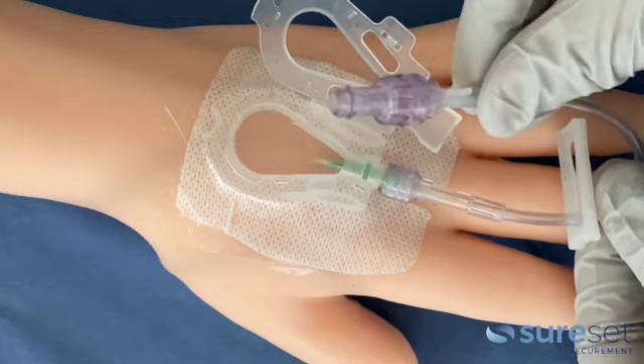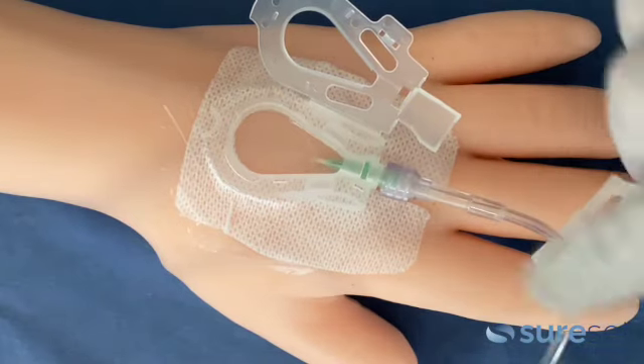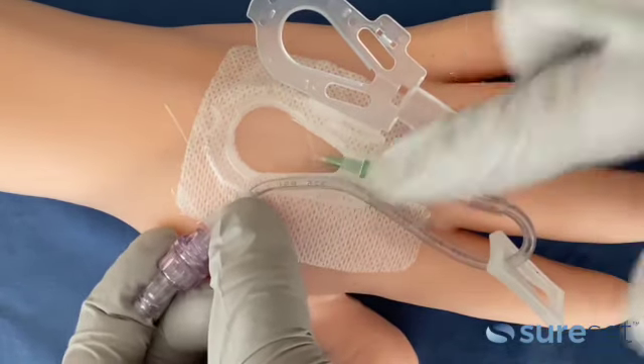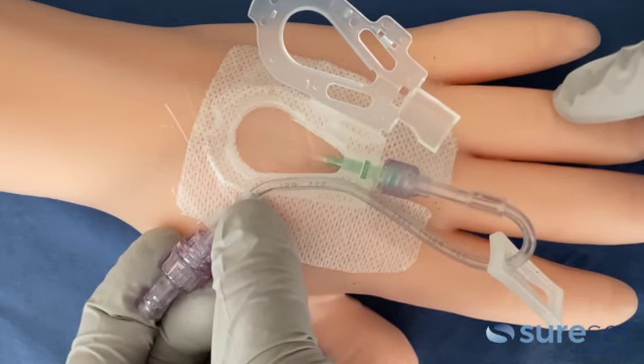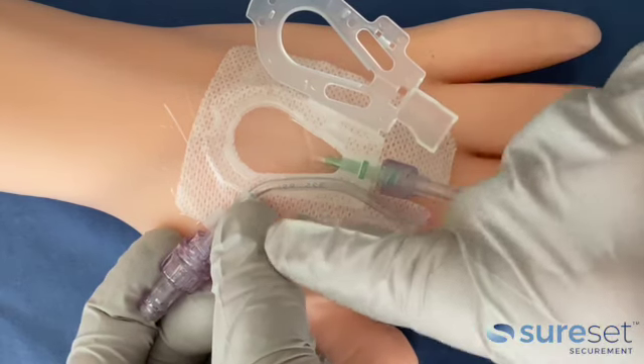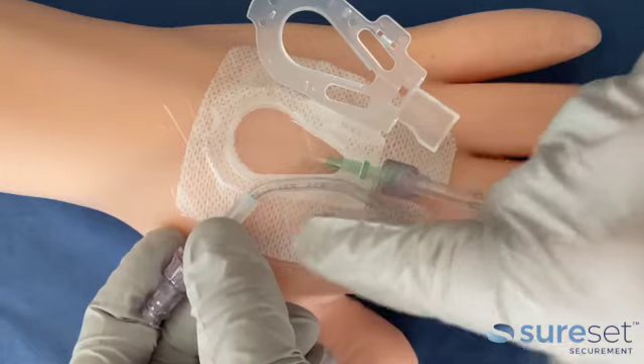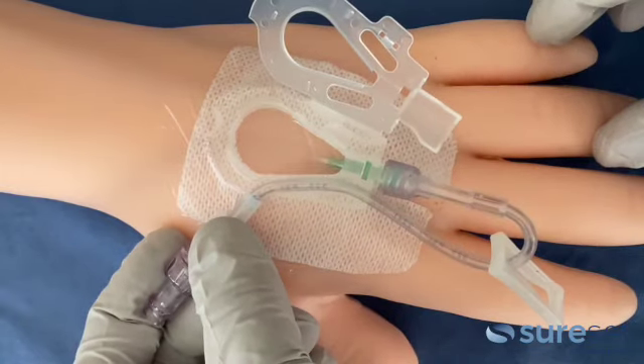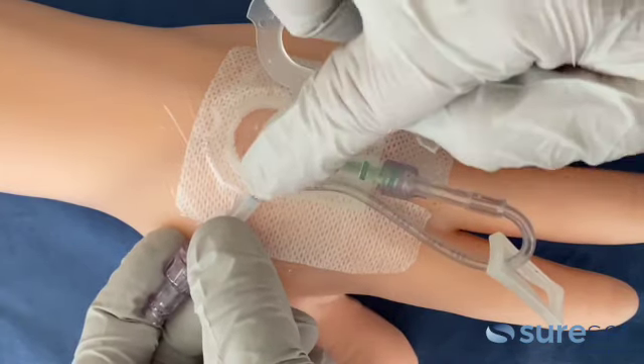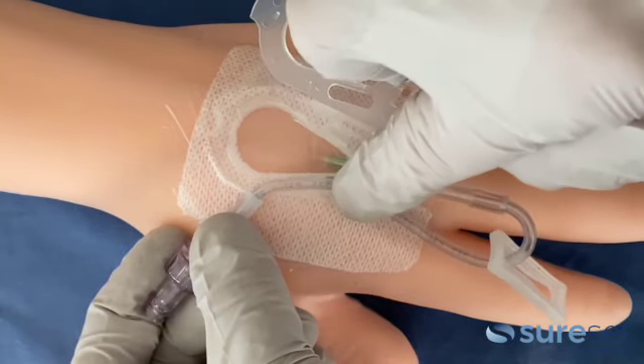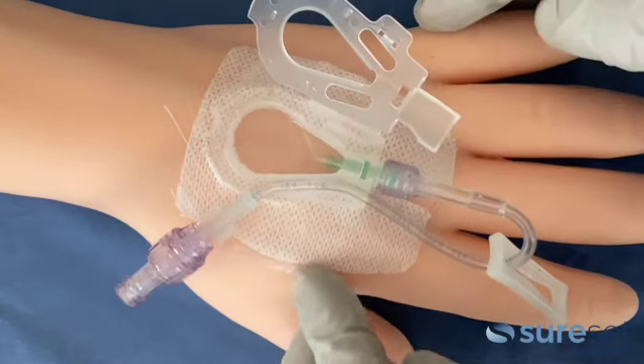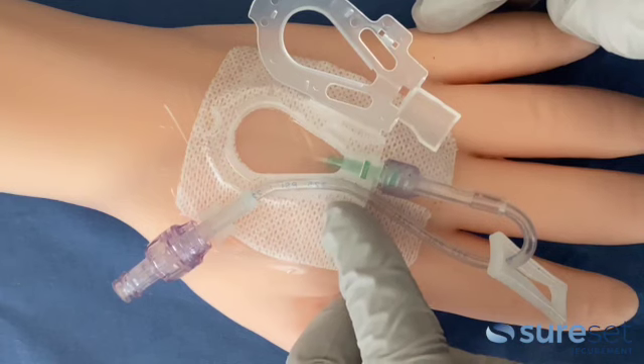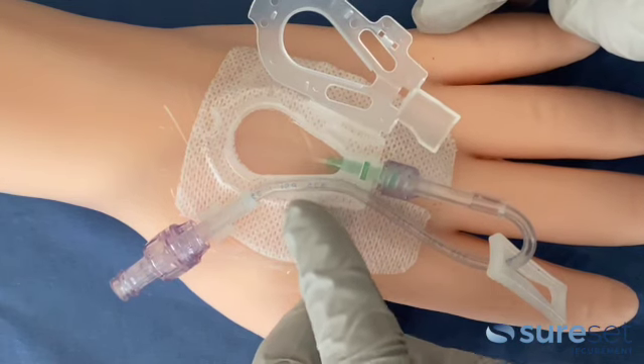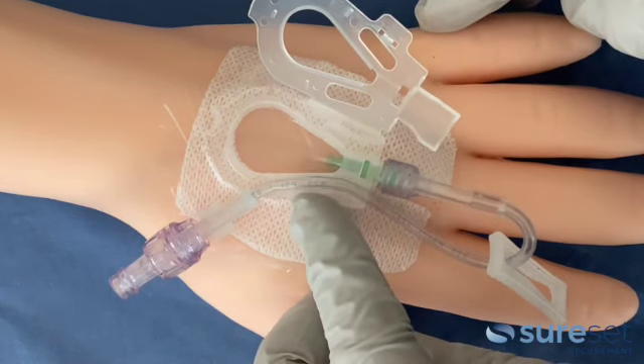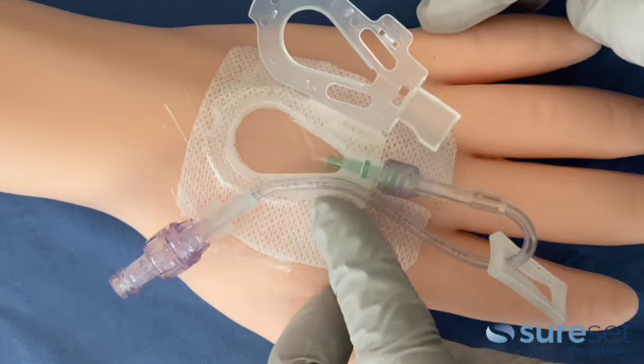Taking into consideration the bending tendency of the IV tubing, the end of the extension set is brought toward the desired lateral channel of SureSet. The grasped portion of the extension set is positioned distal to the chosen channel. The tubing is then pressed into the distal and proximal portions of the channel. There are ledges in the channel to grip the tubing and hold it in the channel. Note: the central portion of the lateral channel has a hump that does not allow the tubing to be pressed into the channel.